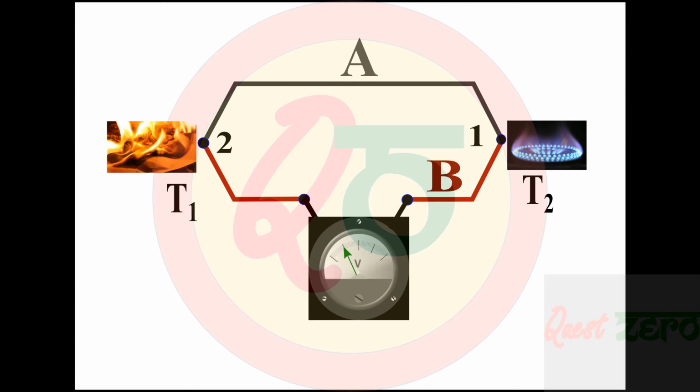So for taking this principle to measure the temperature, what we generally do is, we will make one of these two junctions a constant or a value that could be determined. So for example, junction 1 will be treated as a reference junction, wherein the heat being supplied at junction 1 can be controlled, thereby keeping the temperature at junction 1 as a reference or known temperature.